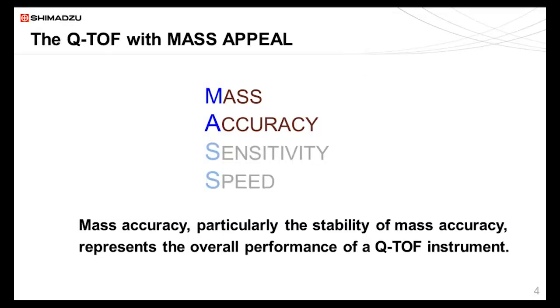How we came to this is by focusing on the MASS appeal, with MASS standing for mass accuracy, sensitivity, and speed. Today I will focus particularly on the mass accuracy and the stability of mass accuracy, which I believe represents the overall performance of a Q-TOF as a high-resolution accurate mass instrument.